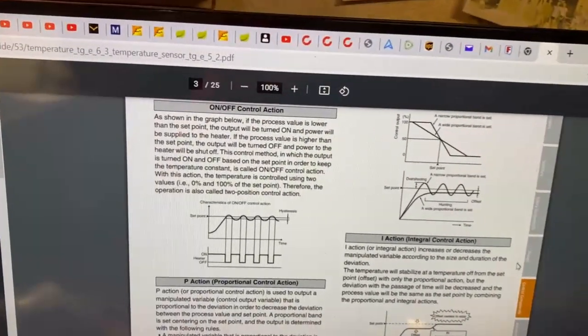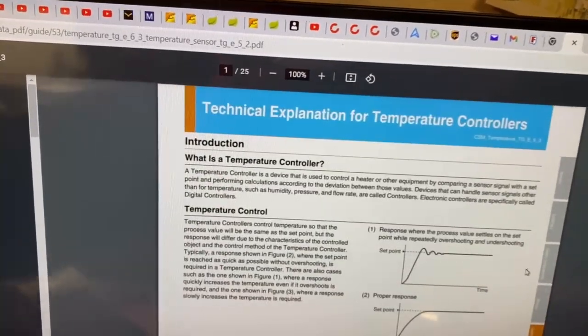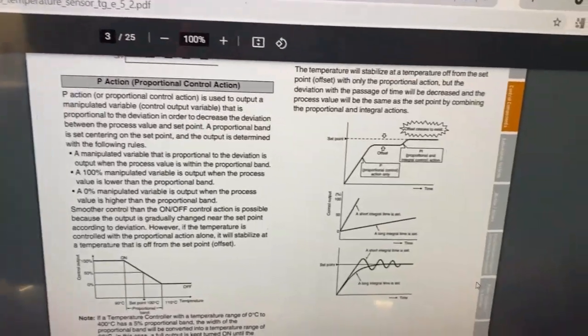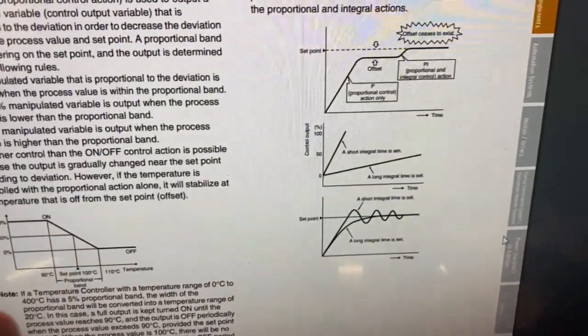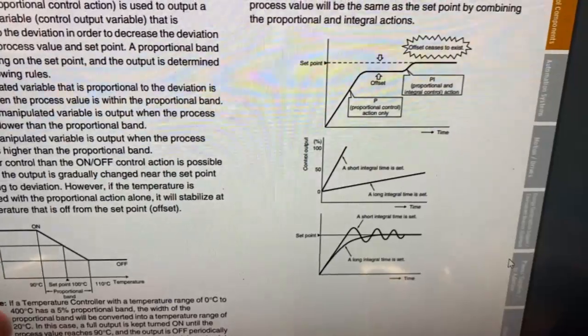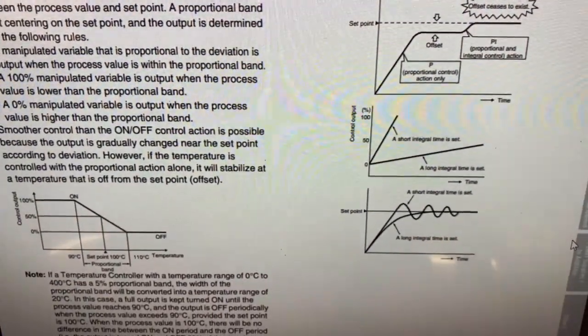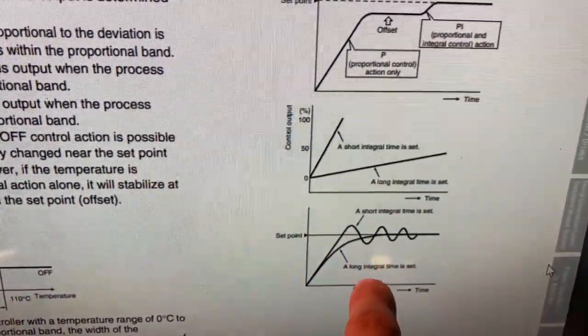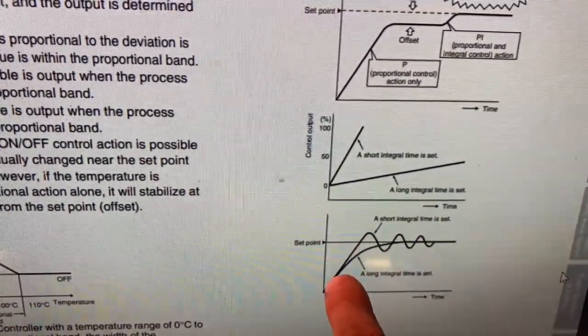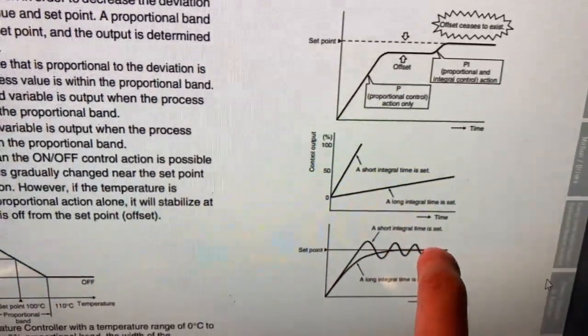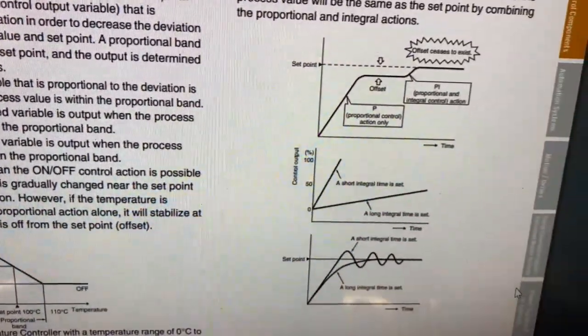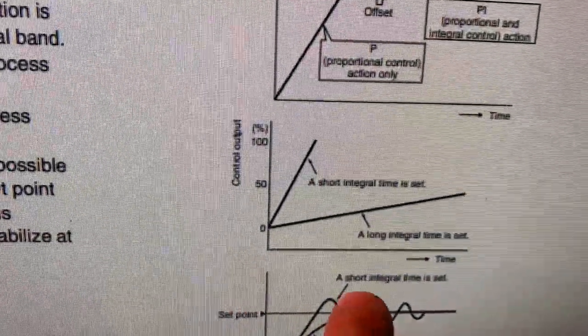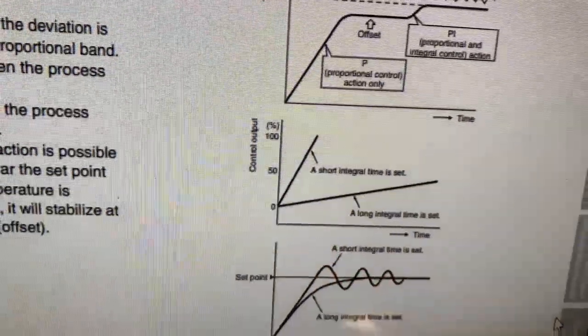So if your name is not Ken and you came to this video for some in-depth information and I'm falling short here, I'm gonna geek out a little bit and we'll get down to some details for just a second here. Let's say you're running this temperature sensitive process or the geometry of your system is such that you need to pay better attention to these details. Let's say you want to set the integral and the amount of time it takes for your system to get up to the set point is too long. So you want to adjust it, but if you adjust it too much then it starts to overshoot and do all this other weird stuff. So let's look at integral for a second.